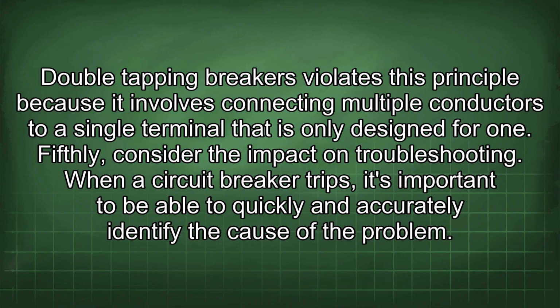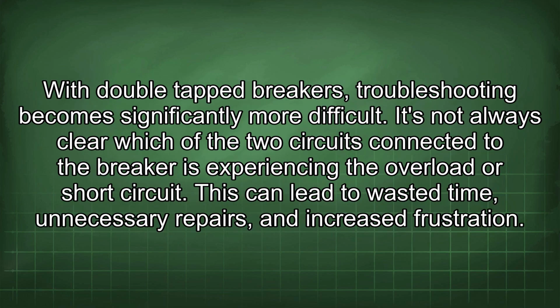Fifthly, consider the impact on troubleshooting. When a circuit breaker trips, it's important to be able to quickly and accurately identify the cause of the problem. With double tap breakers, troubleshooting becomes significantly more difficult. It's not always clear which of the two circuits connected to the breaker is experiencing the overload or short circuit. This can lead to wasted time, unnecessary repairs, and increased frustration.